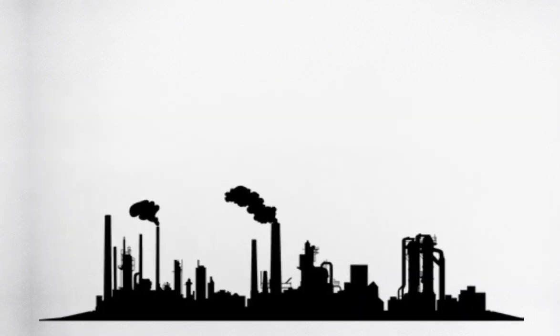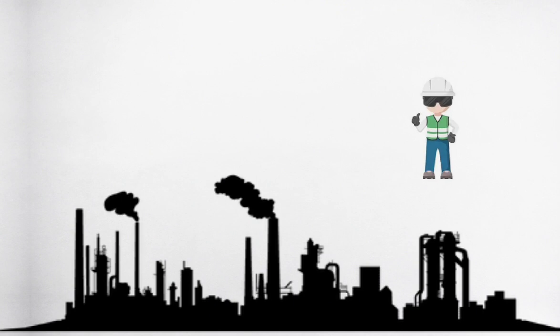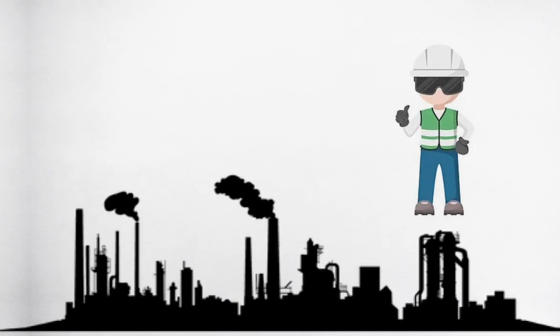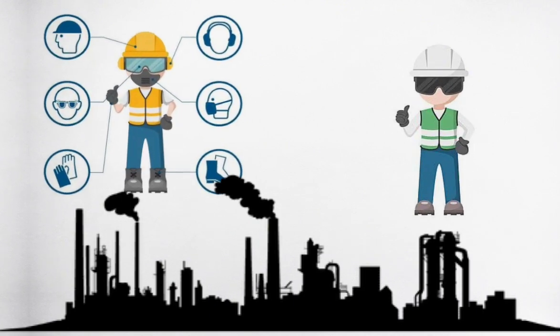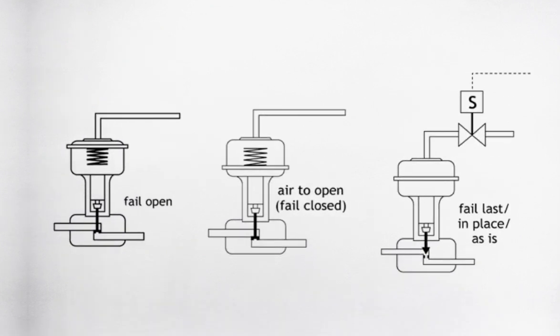Identify the hazards one day before the job. Carry all mandatory personal protective equipment (PPE) and special PPE if required. Check the valve fail action and air filter regulator set pressure from the data sheet of the control valve.